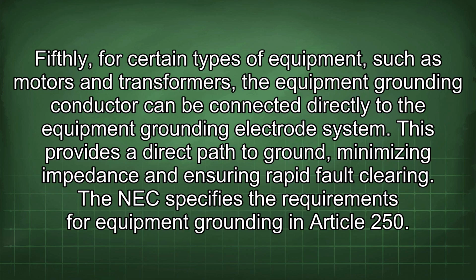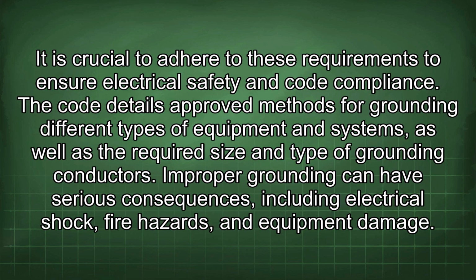Fifthly, for certain types of equipment, such as motors and transformers, the equipment grounding conductor can be connected directly to the equipment grounding electrode system. This provides a direct path to ground, minimizing impedance and ensuring rapid fault clearing. The NEC specifies the requirements for equipment grounding in Article 250. It is crucial to adhere to these requirements to ensure electrical safety and code compliance.